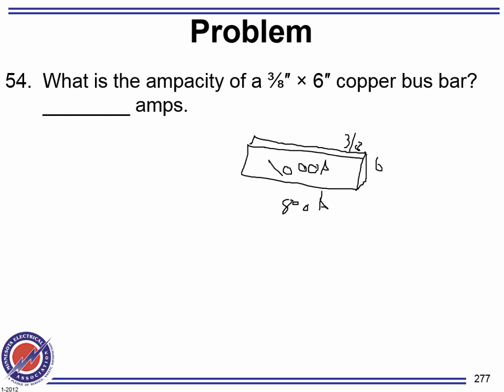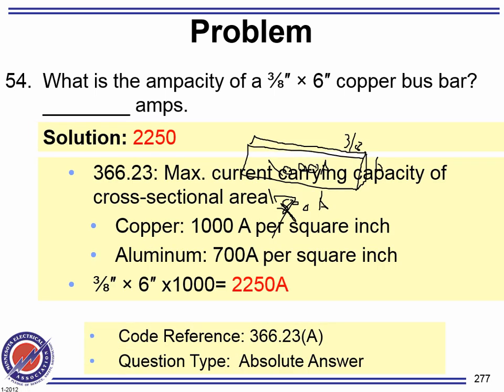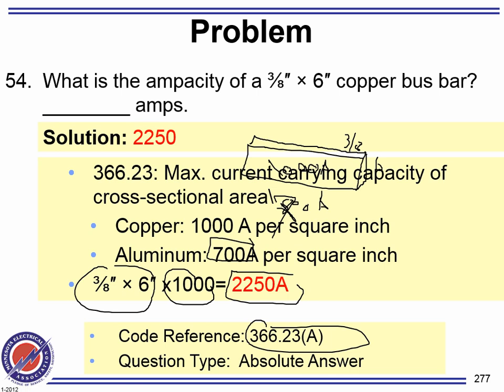Copper or aluminum. What did they give for 700? I'm sorry, 700. I lied to you. 700 if it's aluminum, 1,000 if it's copper. All right, piece of cake. Then here's the dimension of that cross-sectional area multiplied by 1,000, which gives you 2250. If it's aluminum, what do you do to it? Multiply by 70%. Aluminum is 70% of the copper. Could be right here. 366.23(A), I believe. Should be in there.